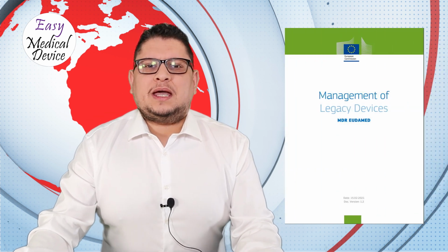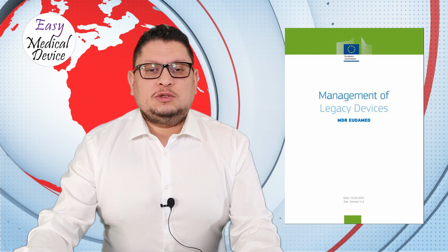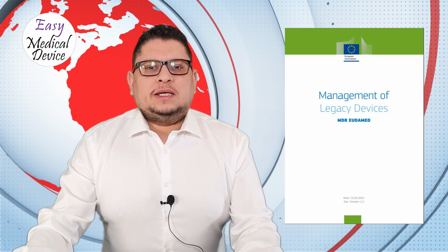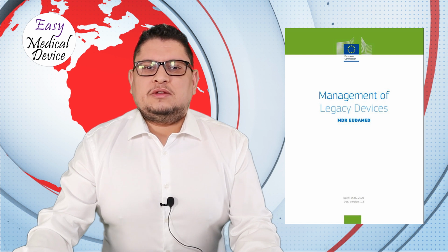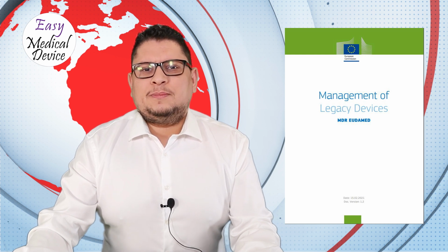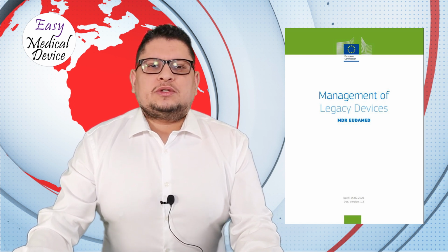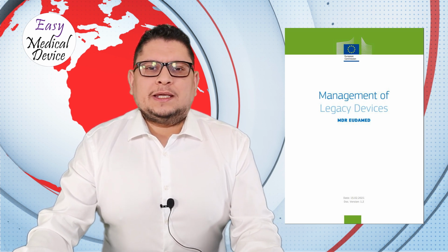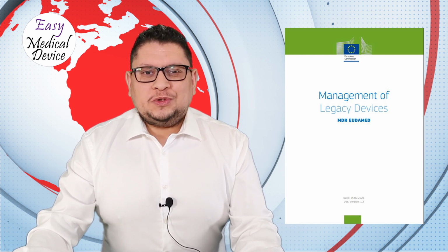You have to understand that normally EUDAMED will be used to register EU MDR devices that have a UDI code and everything. But in the case there is an issue on the market with your legacy devices, the devices that are still under EU MDD, how can you register or inform about those devices if they don't have a UDI code? The idea here is that EUDAMED will create a UDI code for your products, and it is explained in this document. And we have new terms to learn.